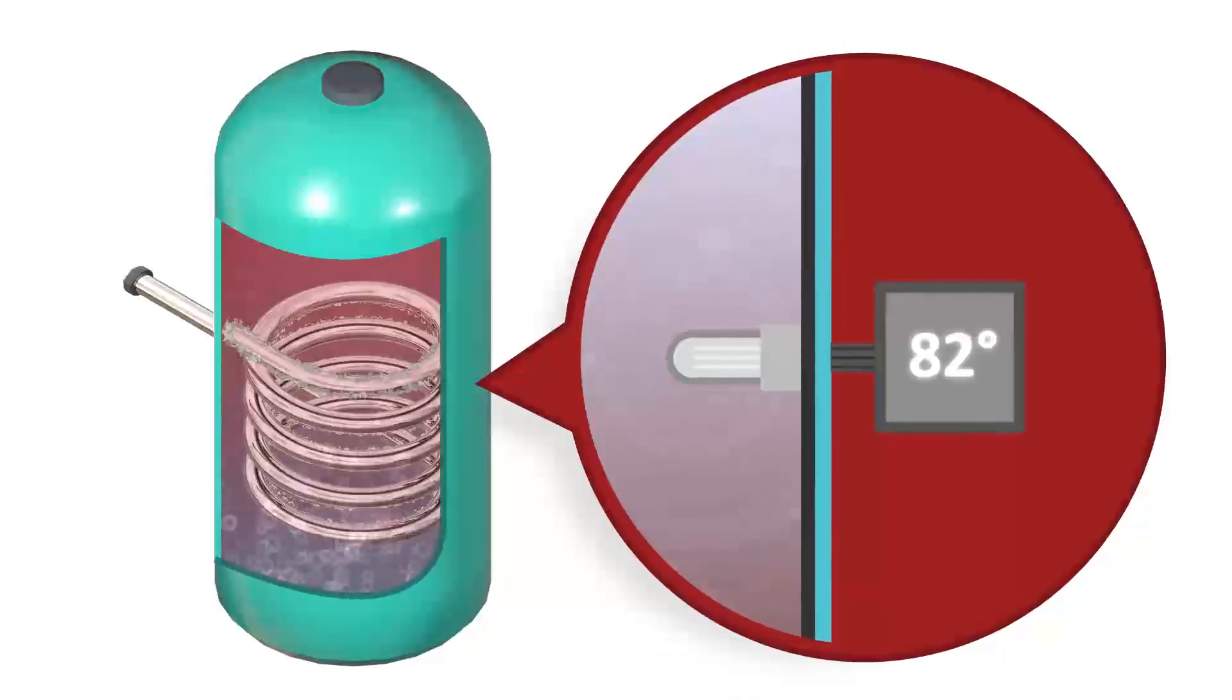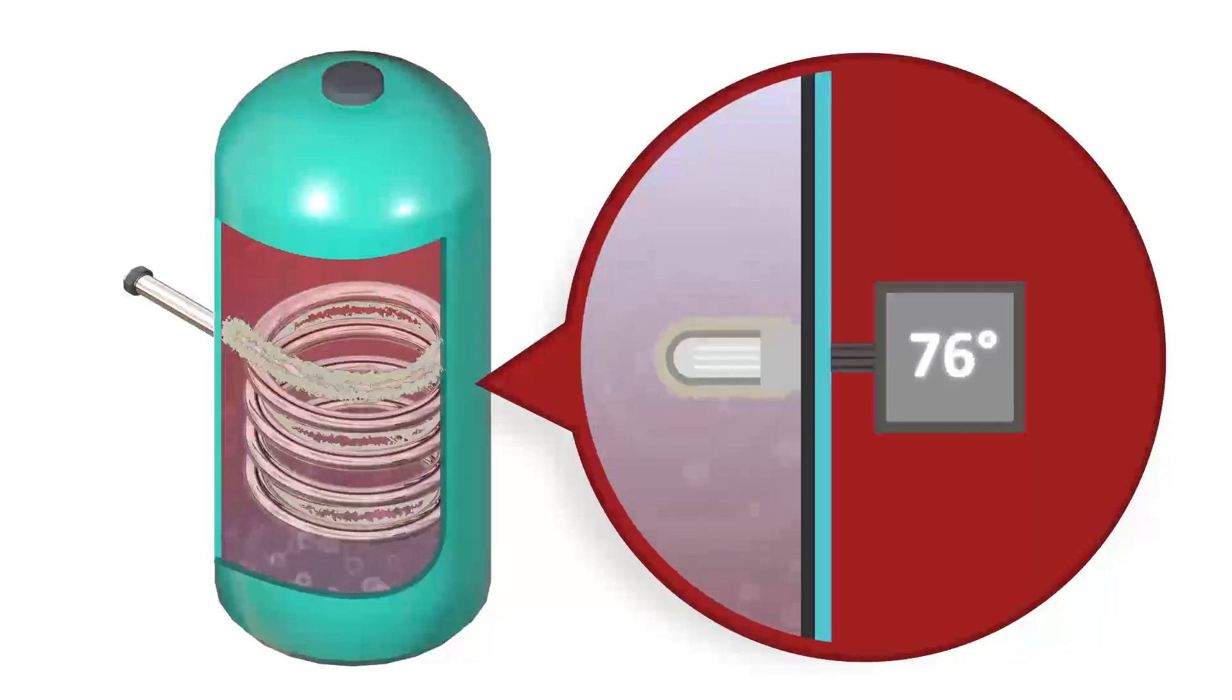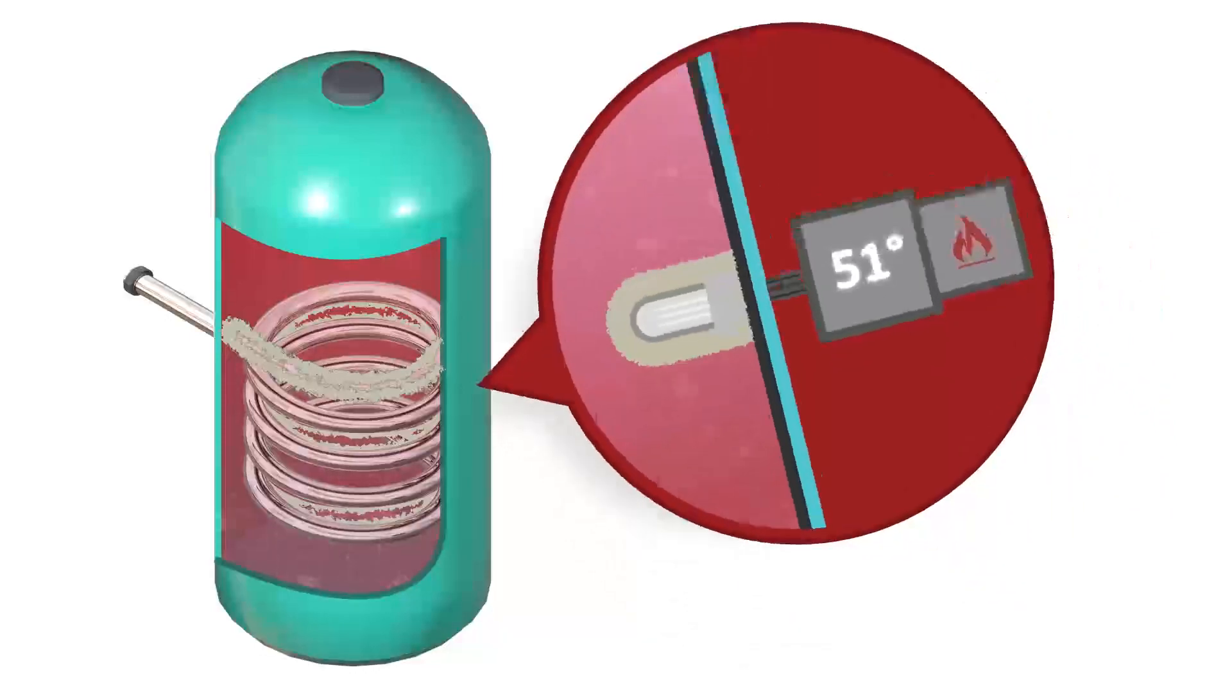Furthermore, scale build up on sensors in heating systems is a major cause of energy waste. When a sensor or sensor pockets get scaled up, it will give false readings to the heating controls and will cause water to be heated to a higher temperature than required. This is particularly important in modern heating systems, as they rely heavily on these sensors, which are in boilers, hot water cylinders and heat pumps.